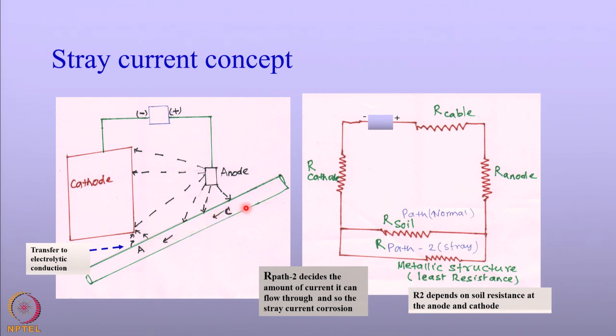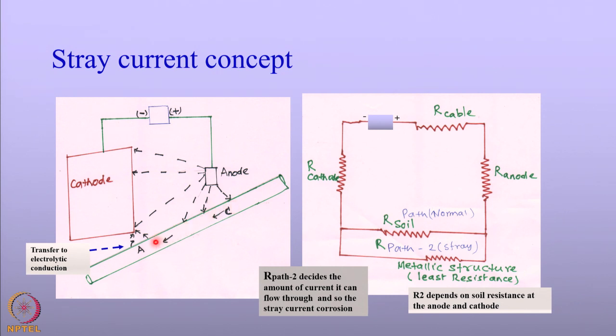The current enters the pipeline and travels along it. The metallic structure has the least resistance compared to the resistance offered by the soil, so the current easily flows along the metallic structure through electronic conduction. This current flow cannot continue forever, because the current has to go back to the circuit and to the rectifier. When the current travels close to the vicinity of the buried structures, the current tries to leave the structure and enters the soil, from where it enters the intended cathodically protected structure and then goes back to the rectifier.